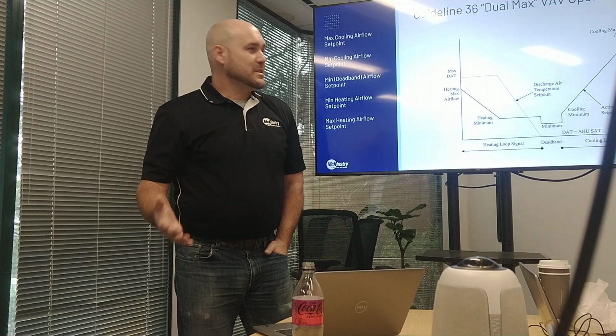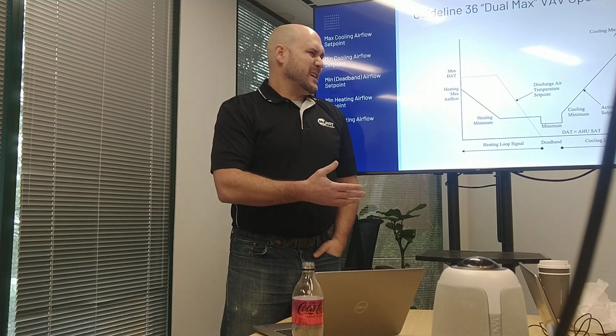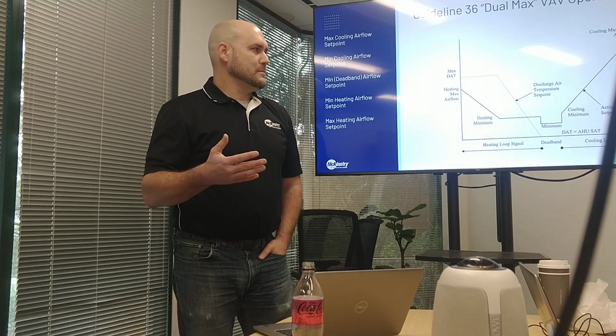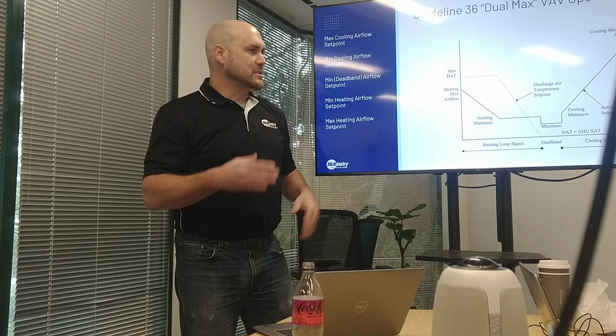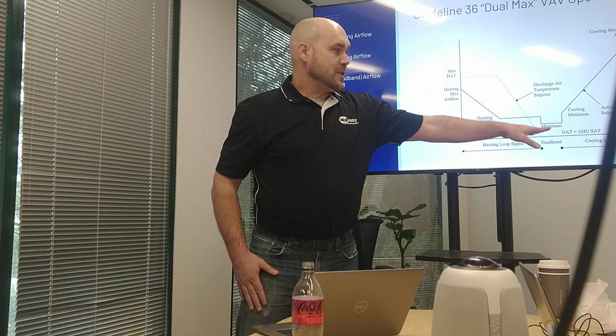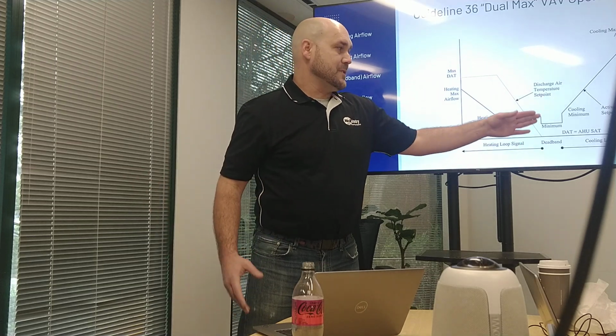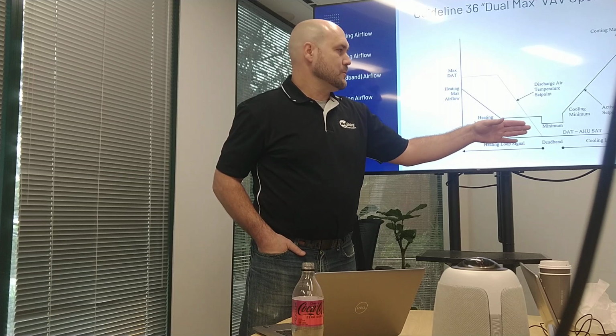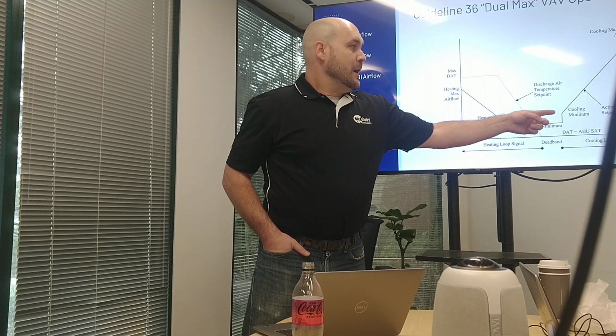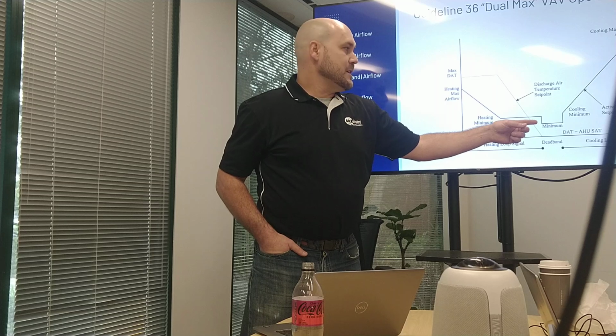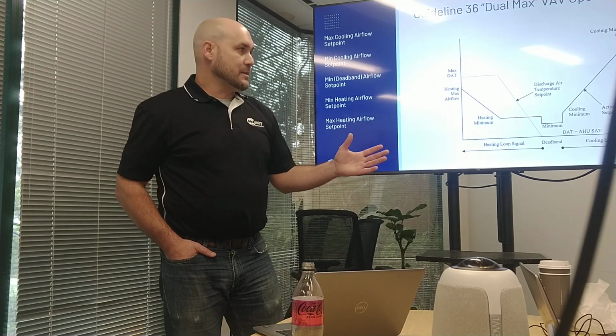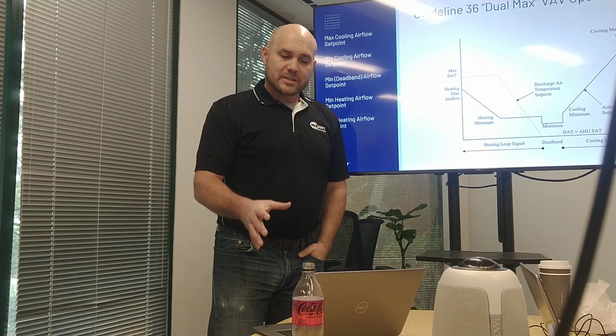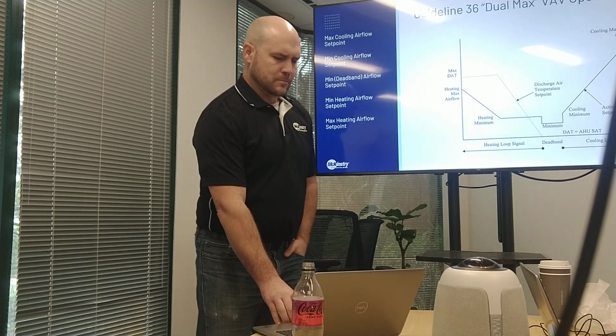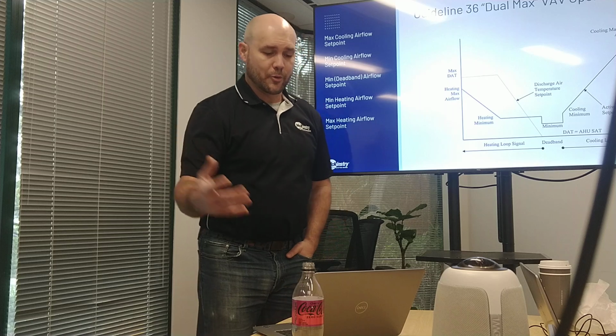In a very simplistic approach, they could all be the same value, but as I mentioned on the last slide, that doesn't tell you at a glance what mode the box is in. So having some differentiation between those 3 values, the cooling minimum, the actual deadband minimum, and the heating minimum, you can see, hey, maybe they're all right around 350, for example. Hopefully a little more thought goes into it, and we'll get into that. But maybe the cooling minimum is 375, the actual minimum is 350, and the heating minimum might be 360. So there's just a little bit of difference between them, so you can see at a glance whether you're close to satisfied or the box is satisfied, and which mode it is actually in, without needing to display yet another point on the graphics.